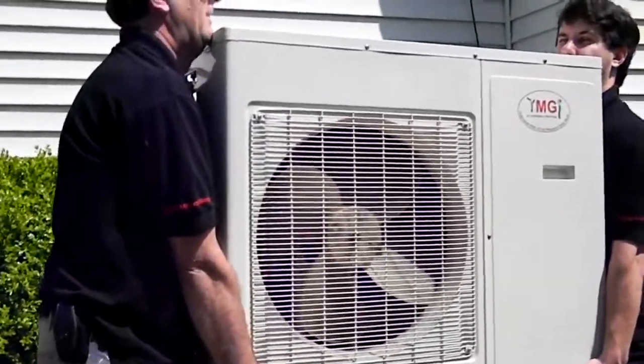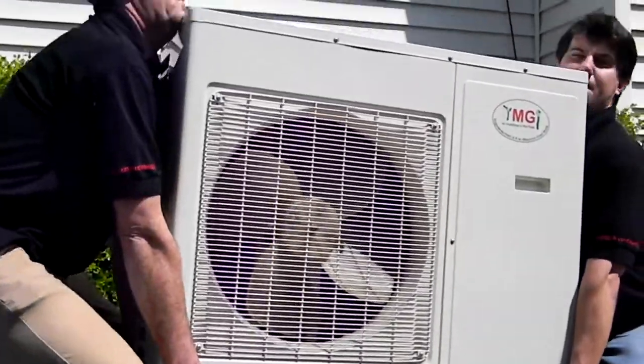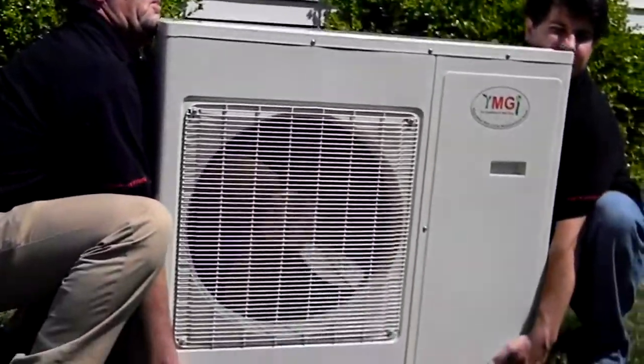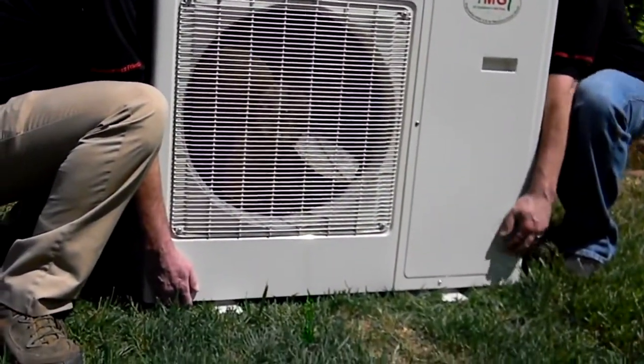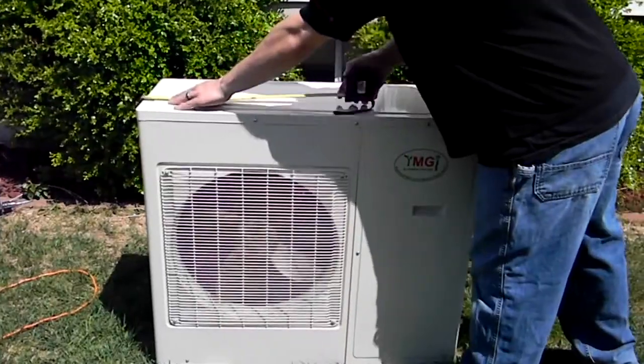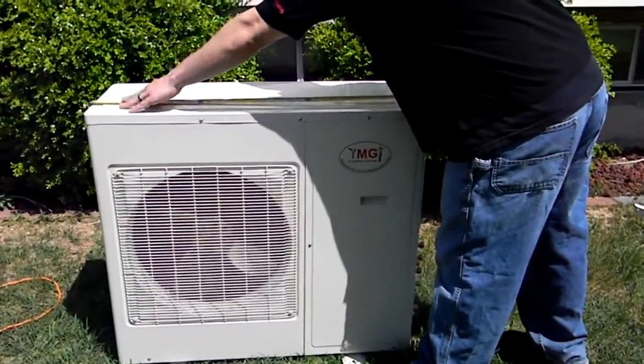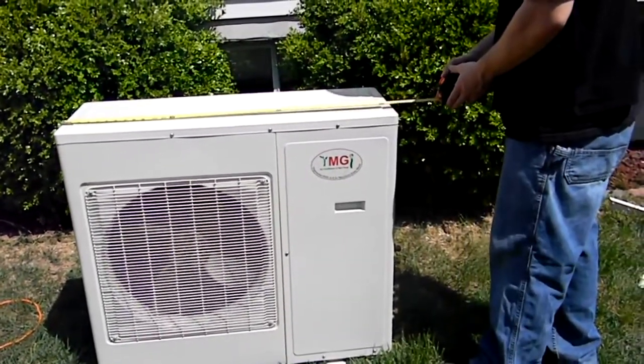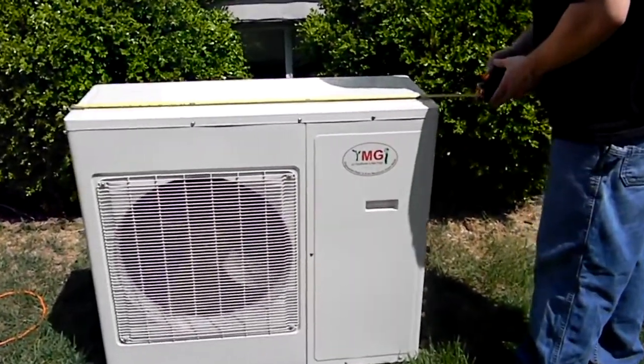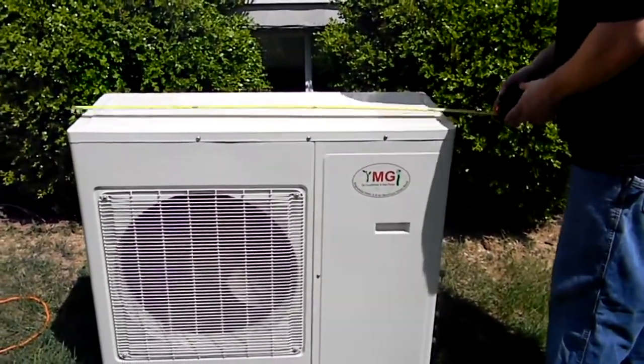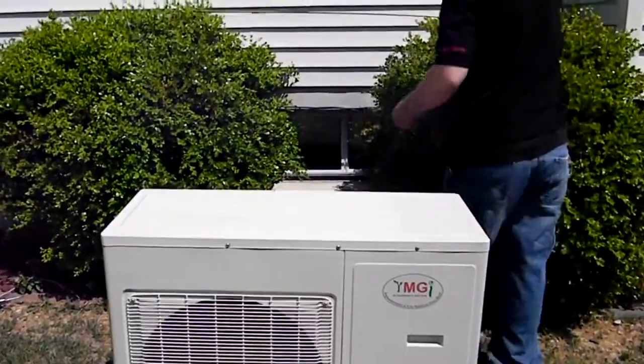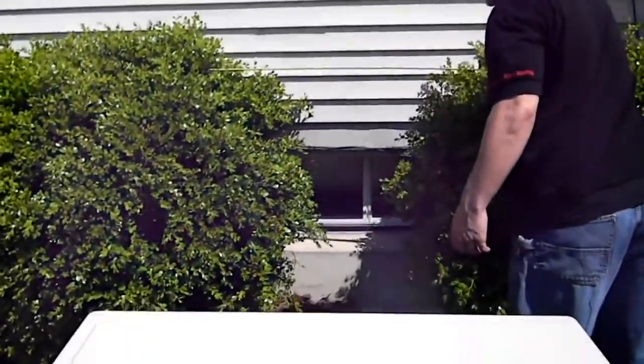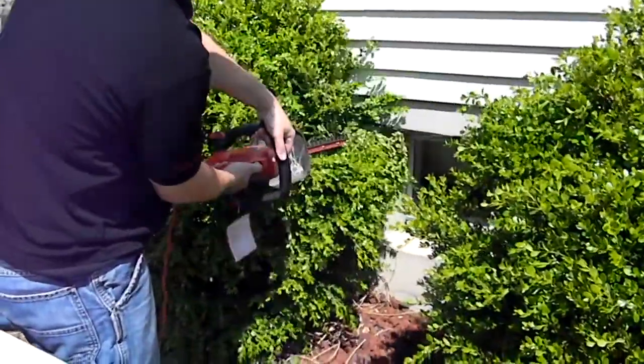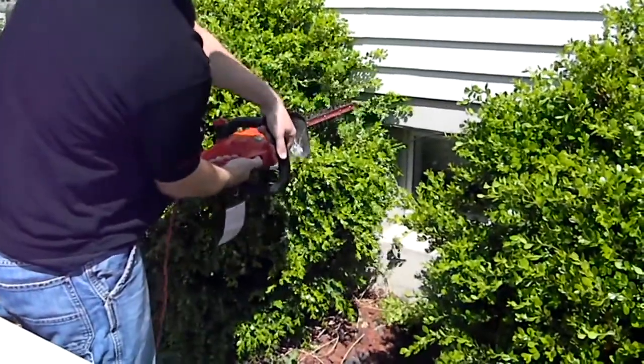Find a location, not in direct sunlight or where there are high headwinds. Allow enough clearance behind and to the sides of the unit for maximum airflow through the coil. Our minimum airspace requirements are 12 inches on the coil sides and 20 inches above the unit and on the line side. Keep any bushes and shrubbery trimmed away from the unit.